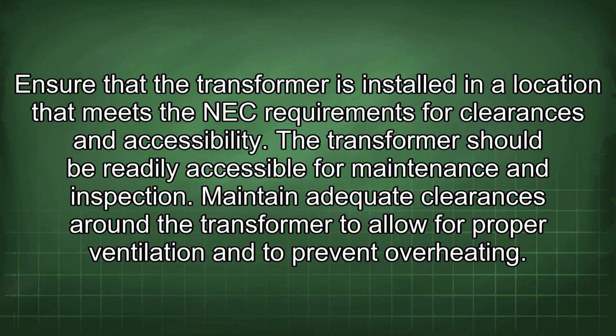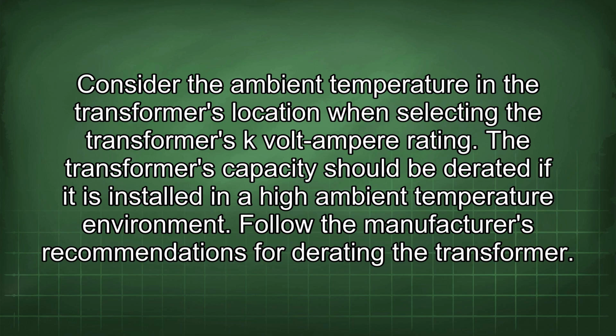Maintain adequate clearances around the transformer to allow for proper ventilation and to prevent overheating. Consider the ambient temperature in the transformer's location when selecting the transformer's kVA rating. The transformer's capacity should be derated if it is installed in a high ambient temperature environment. Follow the manufacturer's recommendations for derating the transformer.